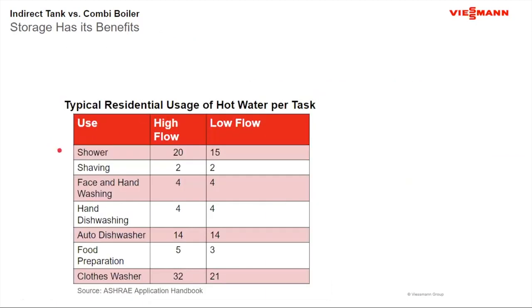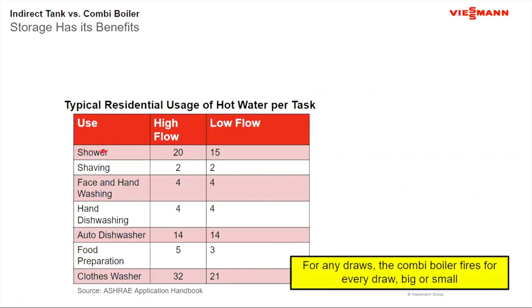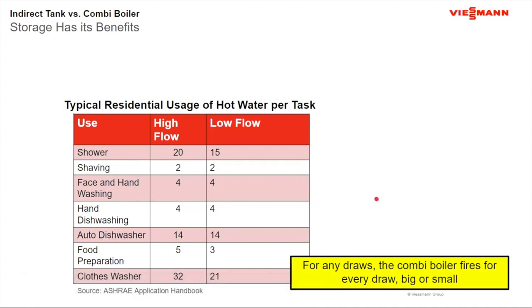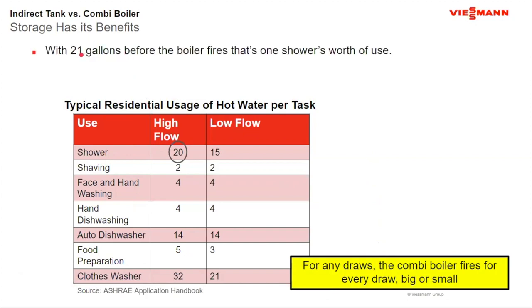Now, if I look at these two numbers, and I come back and look at some of these typical usages, I'm going to actually focus here on the shower, okay? So if I'm taking a shower, I'm using anything, and I have a combi boiler, that combi boiler comes on and it fires. But if I have a storage type water heater, we'll go with the smaller size one, 42 gallon water heater, and I have 20 gallons to work against, the boiler's not going to fire until I use 21 gallons of hot water. So one person can take the typical shower and the boiler never fires because I'm drawing up against that storage. And when that shower is done, they still have 15 gallons of usable hot water, okay?